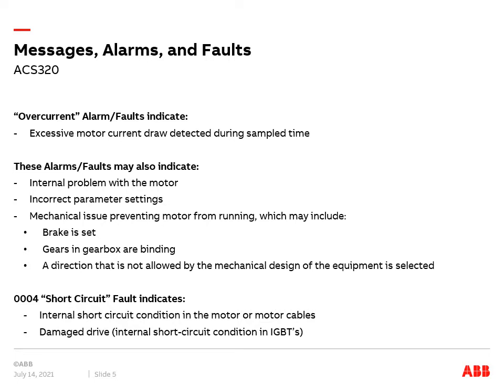Listed are a few mechanical problems that may be encountered that can contribute to overcurrents. Short circuit faults are almost always caused by one of two things: either a short circuit in the motor and motor cables, or a damaged or defective drive.